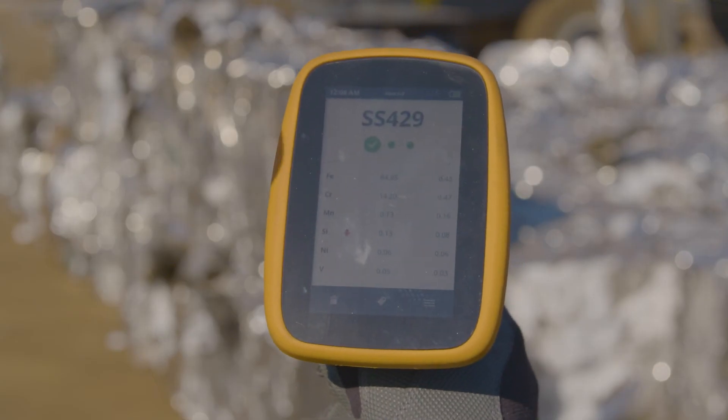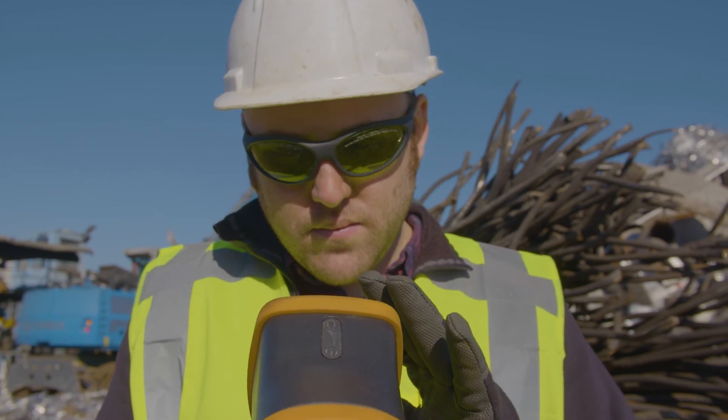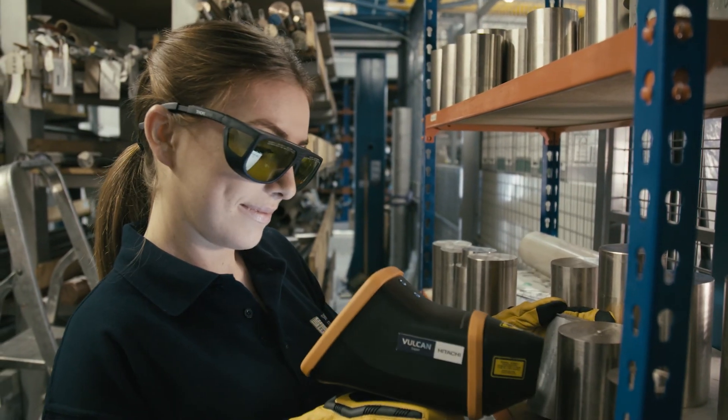From a regulatory and licensing point of view, much less is required from the user than for XRF. Typically no expensive licenses or time-consuming training classes are needed. However, it is important to check your local legislation on issues such as the use of safety goggles. We strongly recommend using safety goggles when operating a class 3B laser device.